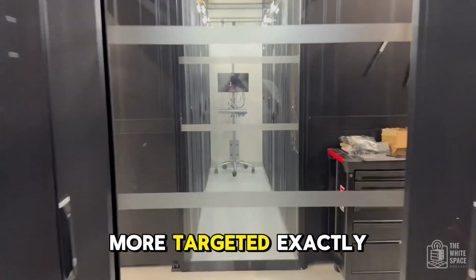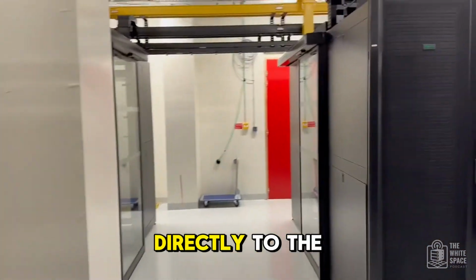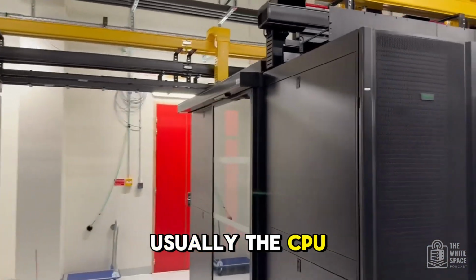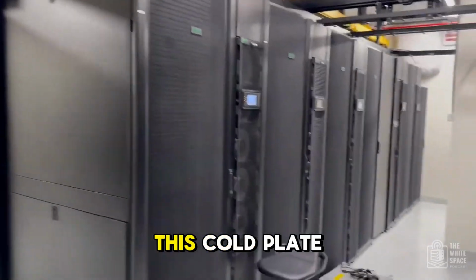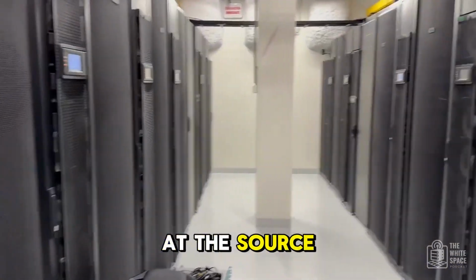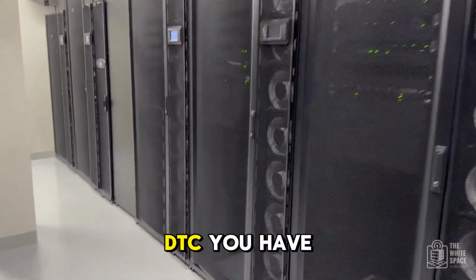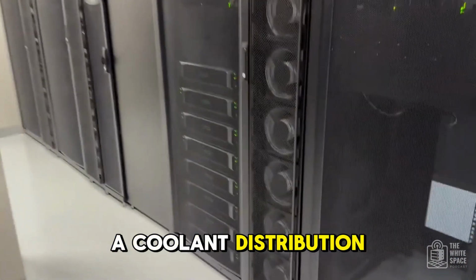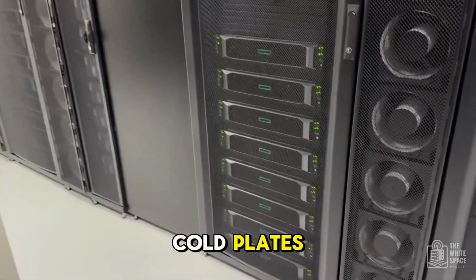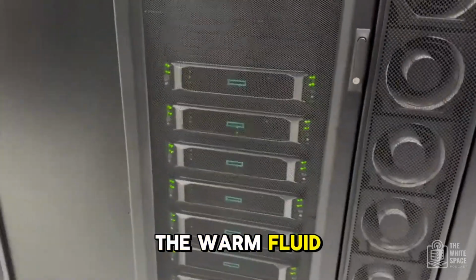Right. Okay, let's shift to direct-to-chip, DTC, cooling. How's this different? More targeted? Exactly. DTC is more focused. You attach a cold plate directly to the hottest components, usually the CPU and the GPU. Coolant flows through this cold plate, absorbing heat right at the source. In single-phase DTC, you have a CDU, a coolant distribution unit, that pumps the fluid through the cold plates in a closed loop. The warm fluid then goes off to a heat exchanger somewhere else to get cooled down again.